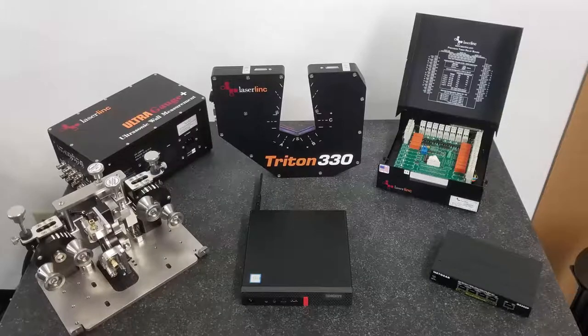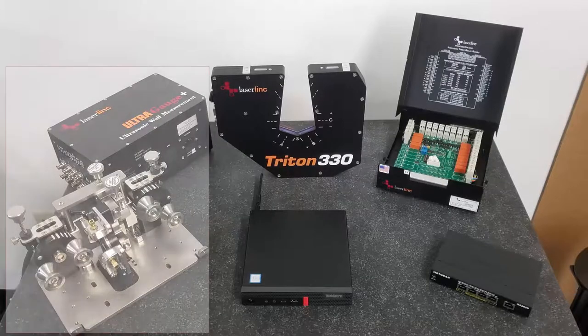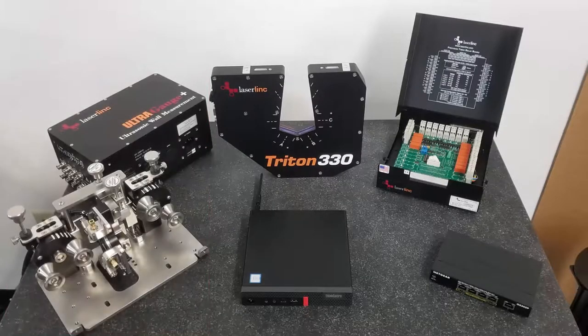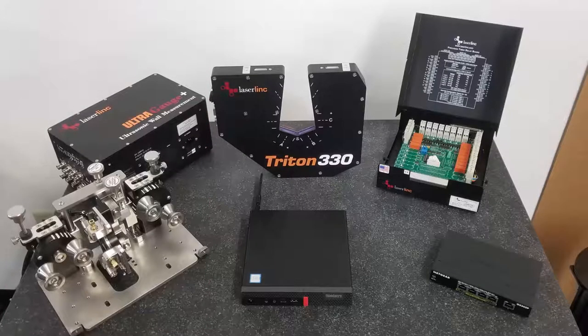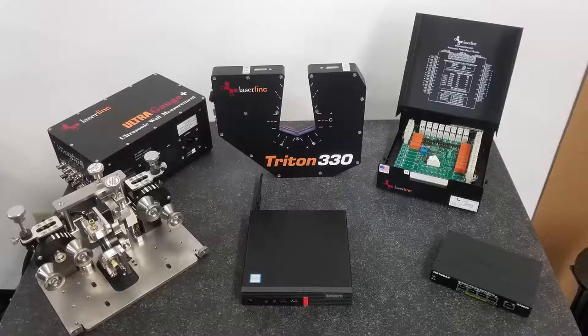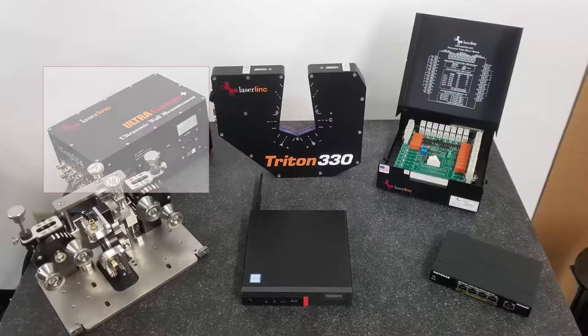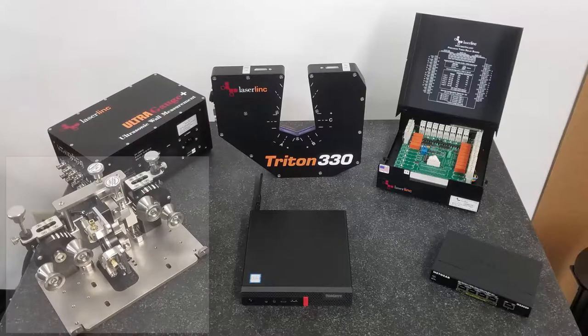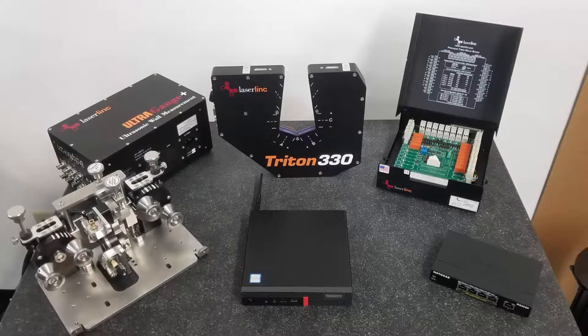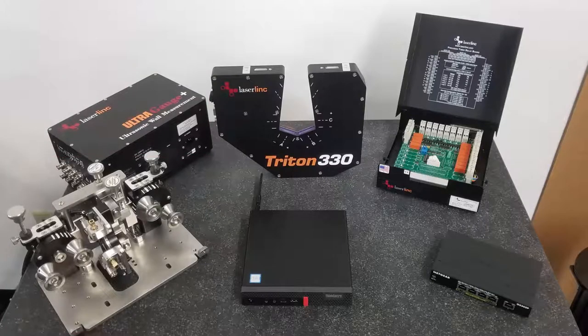Next, we'll look at the ultrasonic portion of the system. The UltraGauge Plus is typically used to measure wall thicknesses of round tubing with thicknesses ranging from 1,000th of an inch to 1 inch or 25 microns up to 25 millimeters and is capable of measuring multiple layers. The ultrasonic component of the system has two parts, the digital signal processor or DSP and the ultrasonic sensor assembly, sometimes referred to as an ultrasonic block.